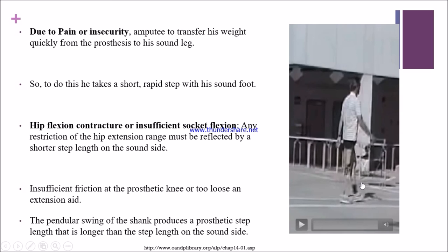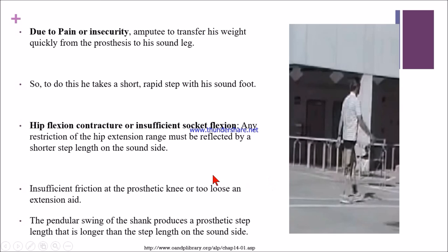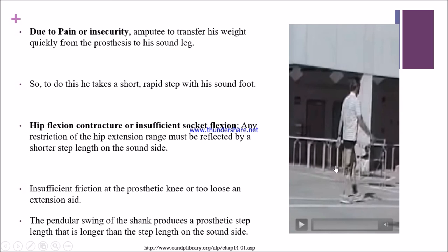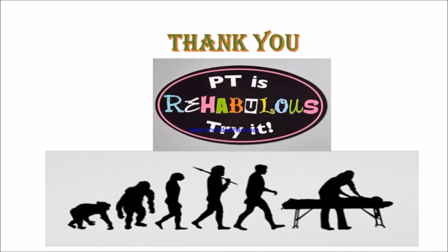If the patient has insufficient knee friction at the prosthetic side or a loose extension aid, this is also responsible for unequal step length. If the pendular swing of the shank produces a prosthetic step length longer than the step length on the sound side, the prosthetic step length becomes unequal.